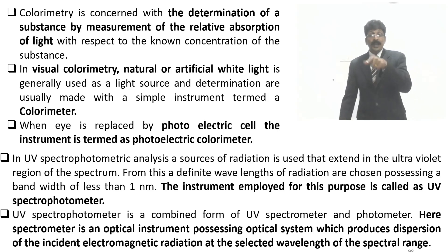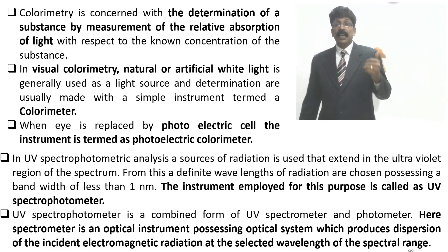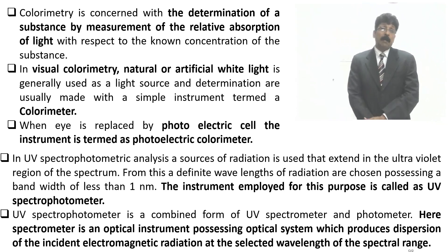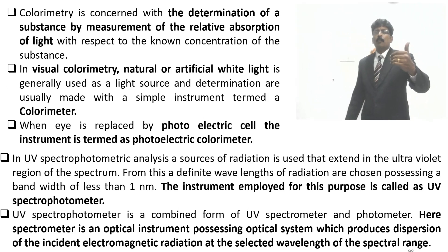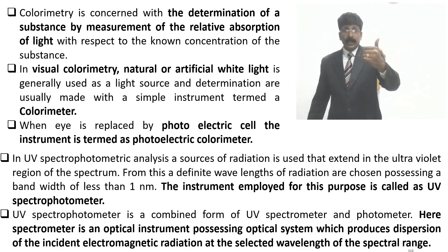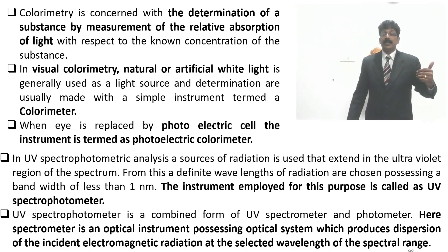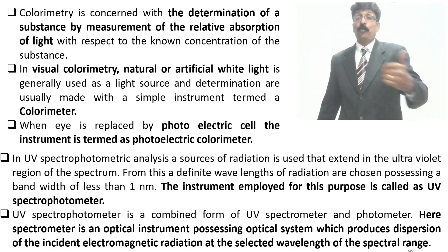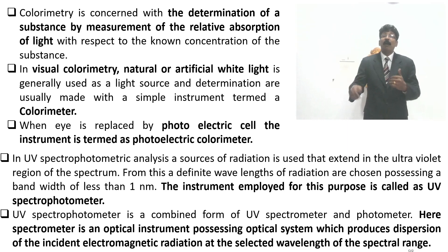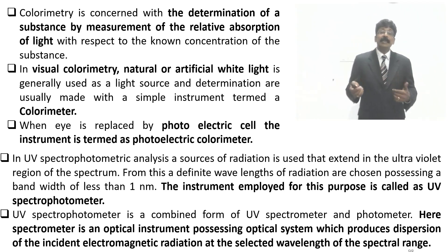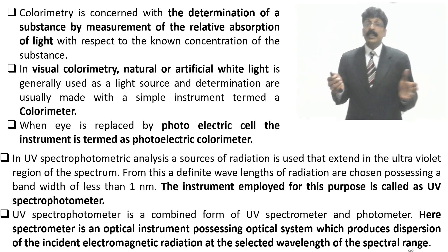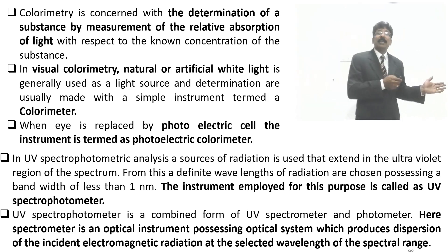UV radiation covers below 400 nanometers down to about 200 nanometers. A UV spectrophotometer combines a diffraction grating to produce monochromatic light in the 200 to 400 nanometer UV range, with a photomultiplier or phototube as detector. The spectrometer is an optical instrument. If using visible radiation the instrument is called a colorimeter; if using UV radiation it is called a UV spectrophotometer.